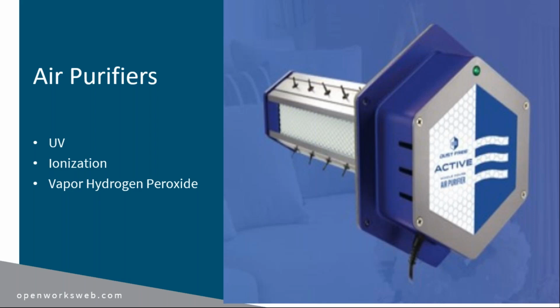Next, we'll talk about devices that can be installed into your HVAC duct systems that are already in place. These are all marketed to clean the air. The three most common strategies for these devices are UV, ionization, and vapor hydrogen peroxide. Although there are many products on the market that claim to clean the air, most utilize the same technologies as what we discussed and may offer only one or up to all three of those.